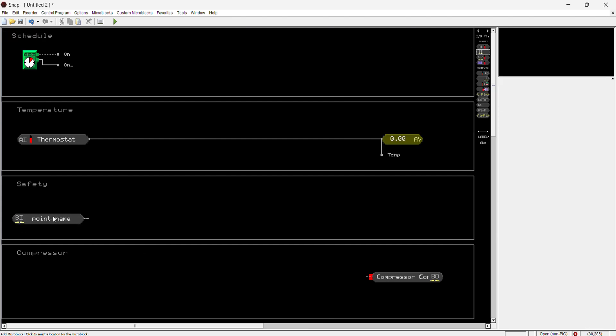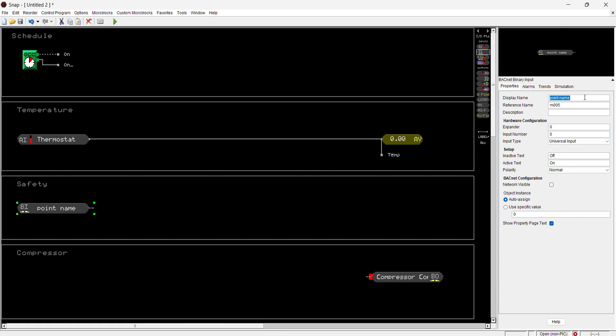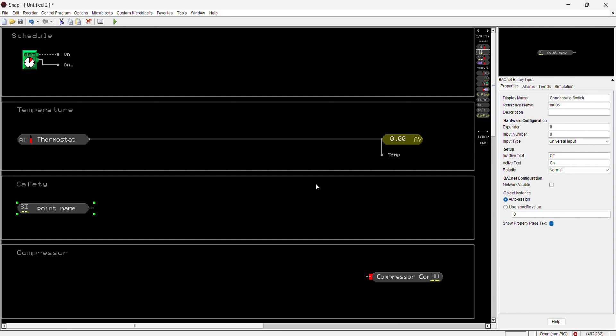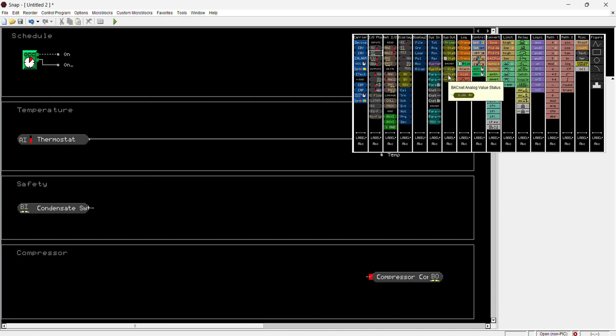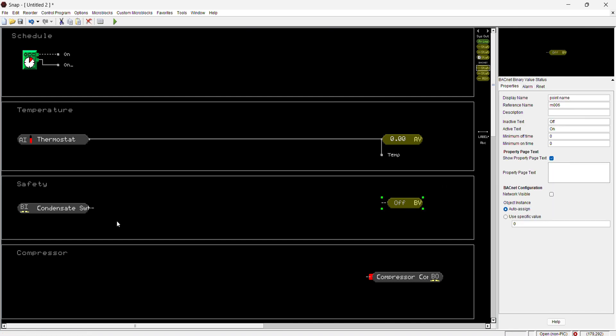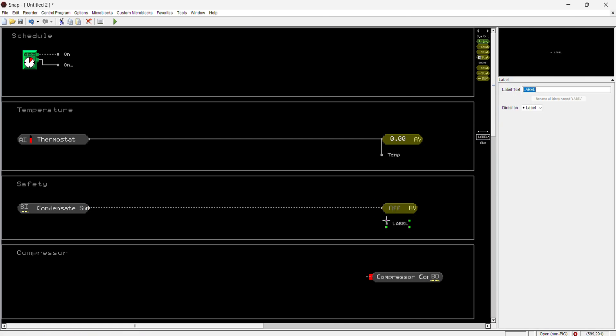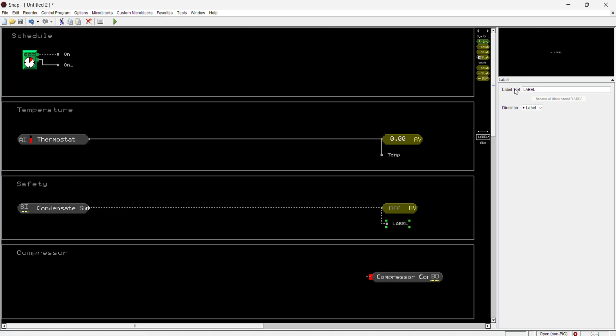Let's put in a binary input, and for this one we can put a condensate switch. As you know, a condensate switch is a normally closed switch — you've got two wires coming out, and there's continuity from one wire to the other. If water goes in and pushes a little plunger up, it opens the contact and stops the 24 volts.